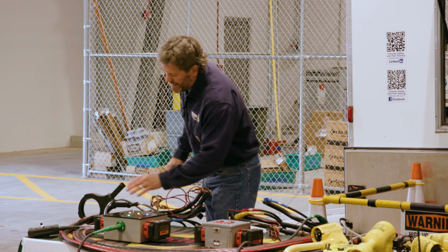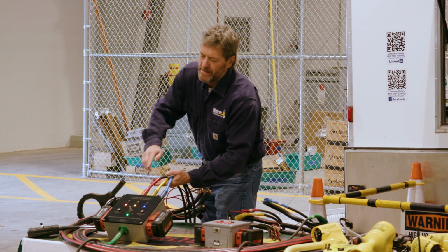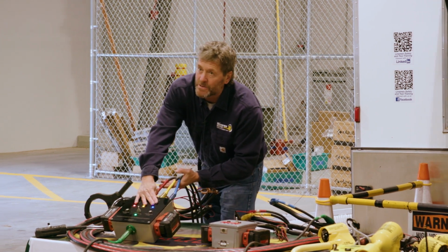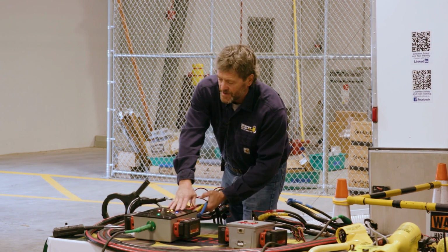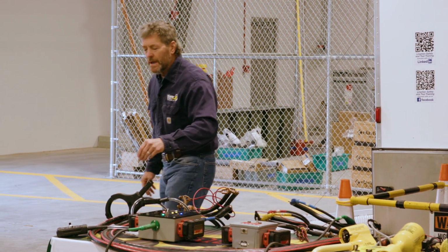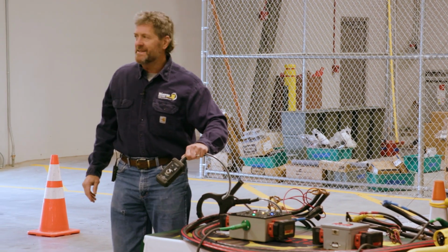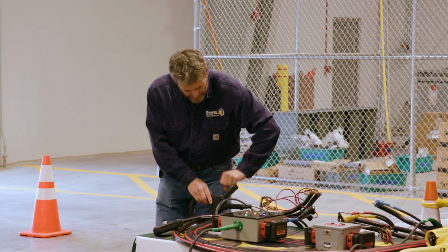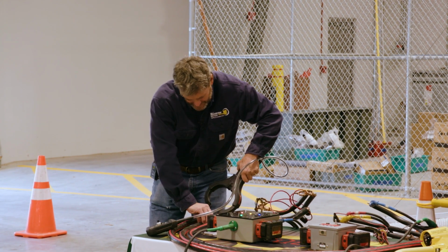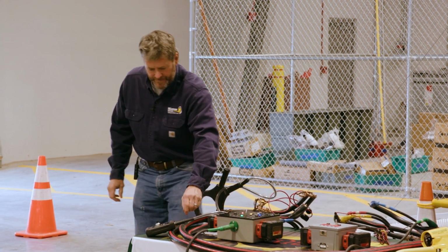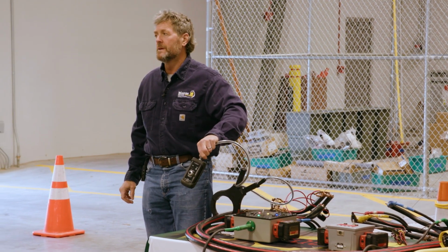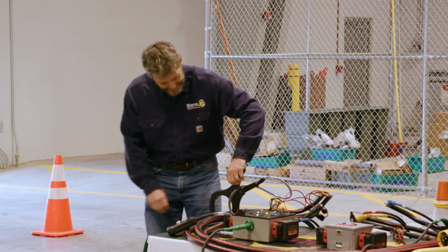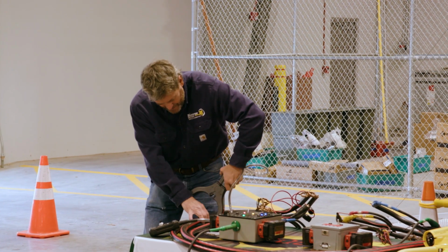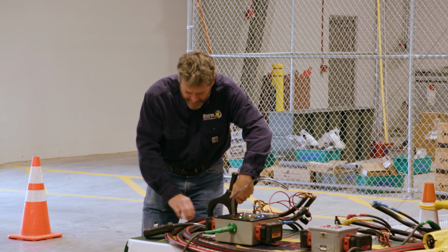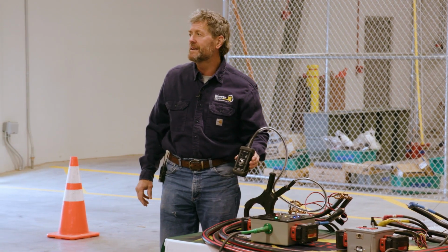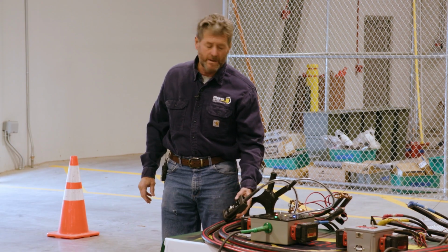All right, so we've got a CT clamp. All the lights are hot. We've got continuity — we have a path back to the tool through the ground. Concentrics are good. So we get one pulse — you see in here, that's an A phase. Go to the next cable: two pulses, that's a B phase. And then you guys probably figured out this next one — three pulses, that's a C phase. Very safe, easy to use, all right?